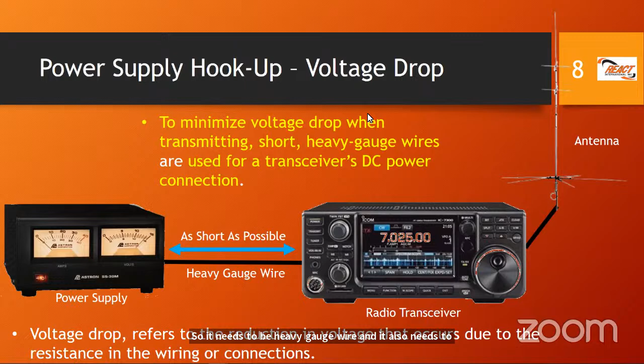And it's an exam question, and it says to minimize the voltage drop when transmitting, short heavy gauge wires are used for transceivers' DC power connection. So what they're trying to say here, when you key your radio, your transmitter, you press that push to talk and you start to transmit, maybe going out at 100 watts, you will experience a voltage drop if this DC power cable is not as good as it should be. So it needs to be heavy gauge wire, and it also needs to be as short as possible. So this is an exam question.